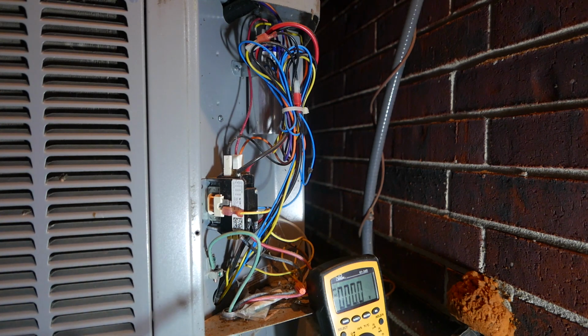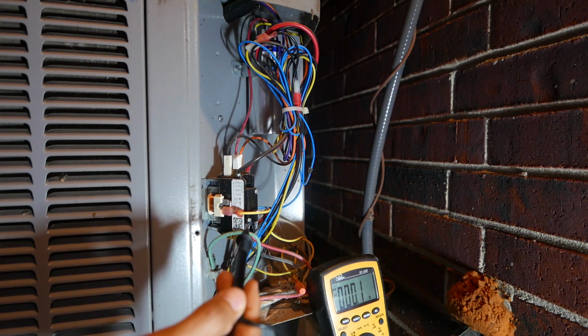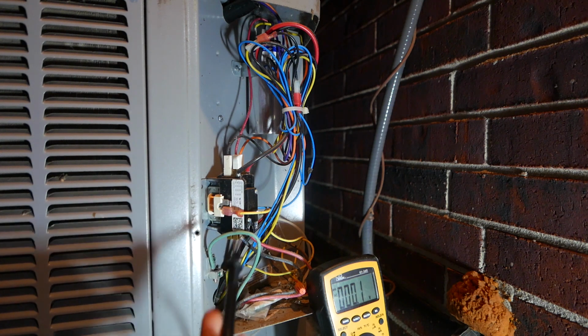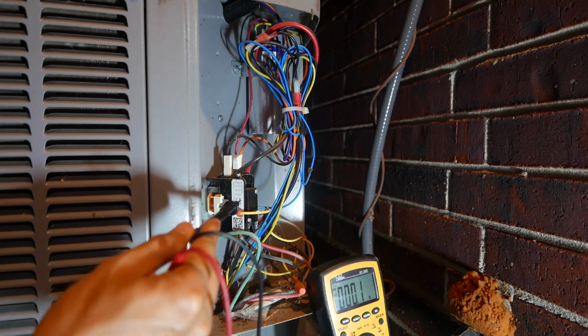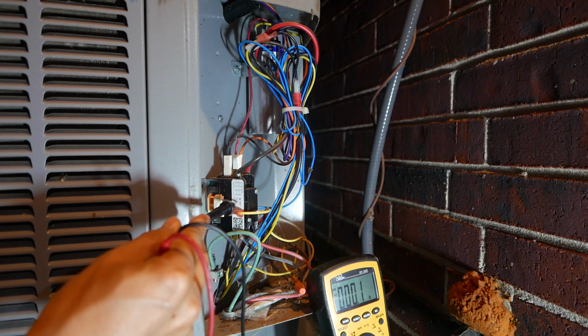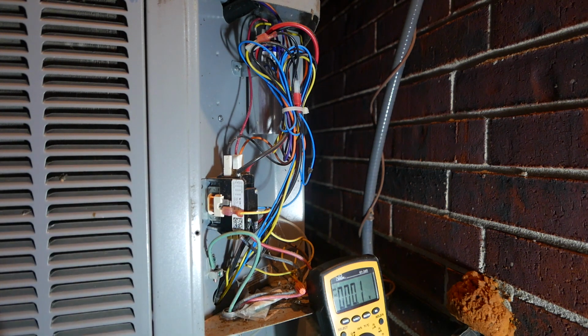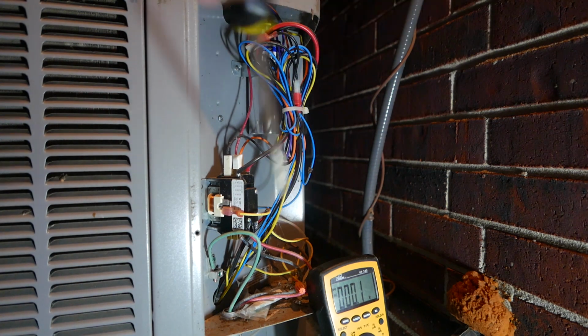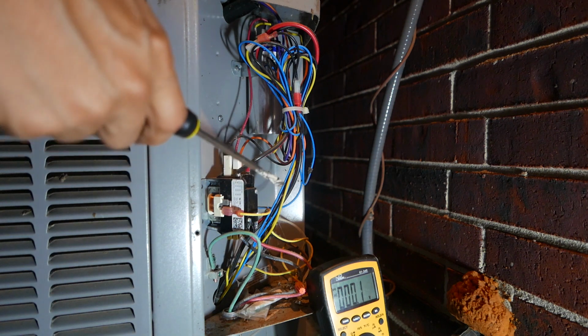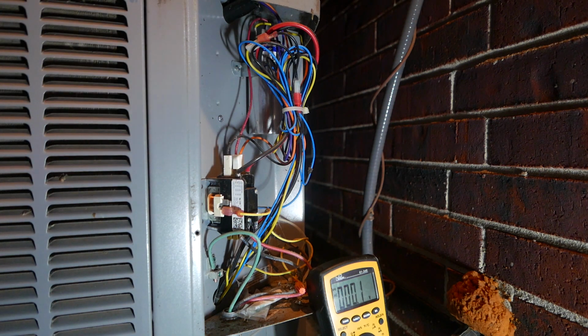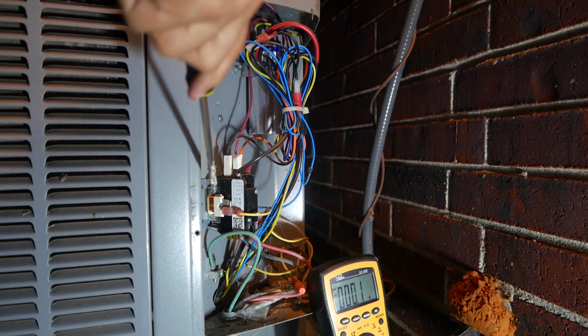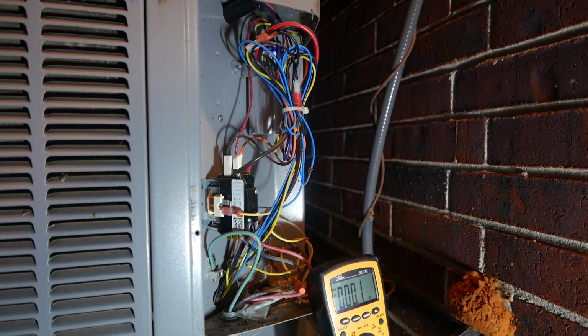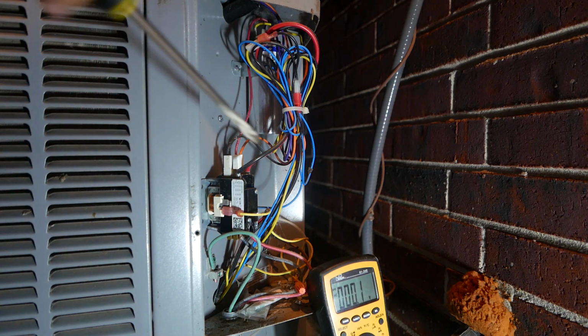So what does that mean? That means that the air handling unit and the thermostat, that's all working. It's sending a signal to the condensing unit, but the condensing unit isn't coming on. This contactor, this relay, is broken. Regardless, I still need to replace this, but I'm just trying to say, if it doesn't want to come on, you can tap it. It might be stuck down there, and you can tap it and it will start working.